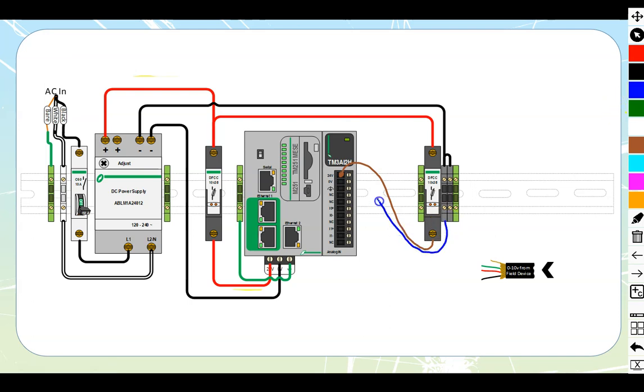Then we're going to take our blue, which is a European standard color for negative, and attach that in over there. Then we're going to take a green or a bond out of that protective earth, and that goes down to my grounding blocks inside my panel. So these three lines have now been used to power up the actual card. Now the card can start to read stuff.